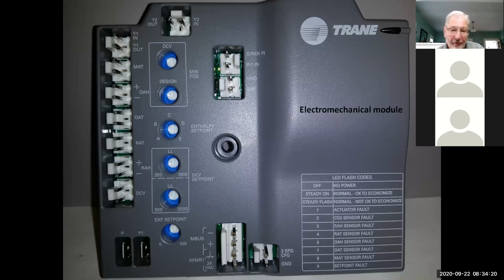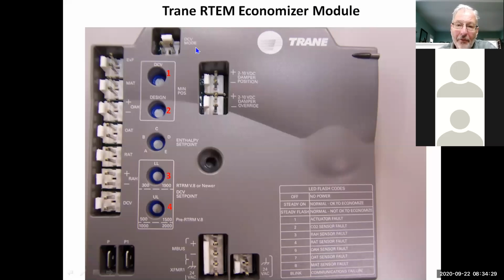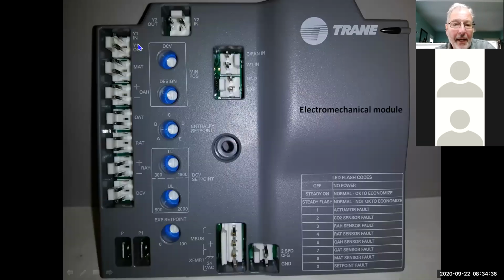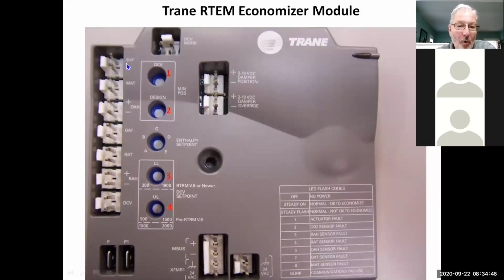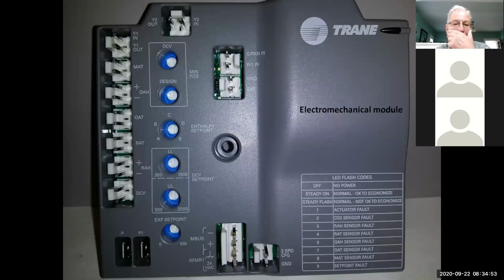What I want to touch on now is how we set up the Economizer. If you look at it, they all look like this today. This is the electromechanical. This is the Reliatel Economizer. They're all kind of similar. The difference is on the electromechanical, we have a Y in and a Y out: Y1 in, Y1 out, Y2 in, Y2 out. On the Reliatel, we don't. It works off the Modbus. It's a communicating system. But the setup is basically the same on both of them.